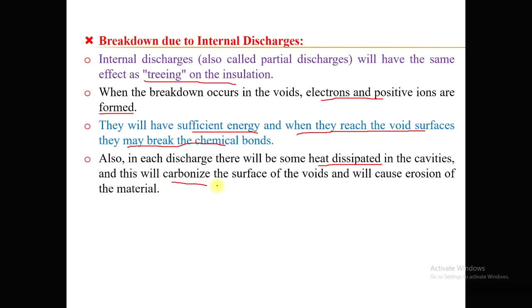Internal discharge is also called partial discharge, and will have the same effect as treeing on the insulation. When the breakdown takes place in the void, electrons and positive ions are formed. These space charges, the electrons, have sufficient energy, and when they reach the surface of the void, they will break the chemical bonds. In each discharge there will also be some amount of heat dissipated in the cavity, which carbonizes the surface of the void and causes erosion of the material.